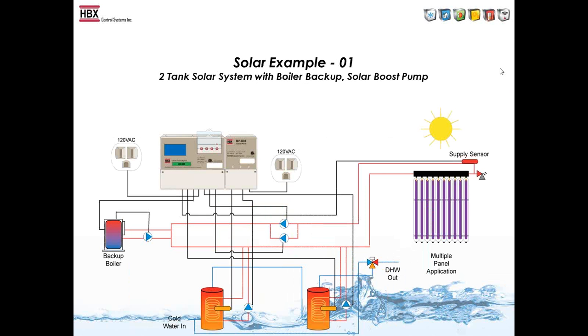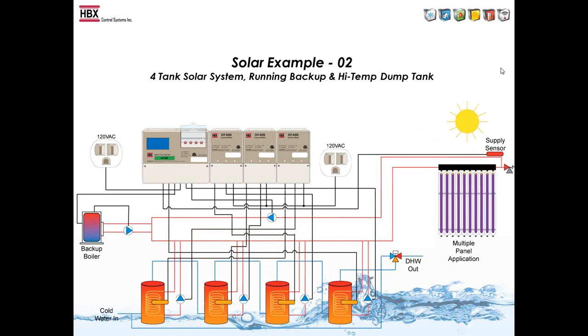This diagram is a two-tank solar system with boiler backup. It shows that it will control your panel, it will control your tanks, it will bring in a backup if it needs to, and it will control all of the pumps in the system. You can also expand the capabilities by adding EXP 300s to it to start running larger solar systems.